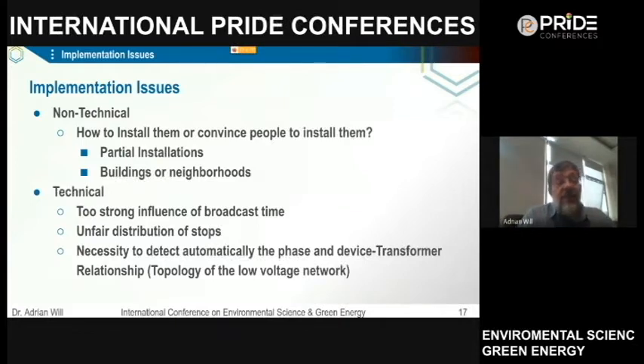And technically, you have 3 points to solve, which we have solved up to today: too strong an influence of broadcast time, so the message has to be really on time, otherwise if you start getting slower or losing packages you will have a problem; an unfair distribution of stops, which we also solved; and it's necessary to automatically detect the phase of the consumer and the device-transformer relationship. You need to know the topology of the low voltage network. I will get into that.